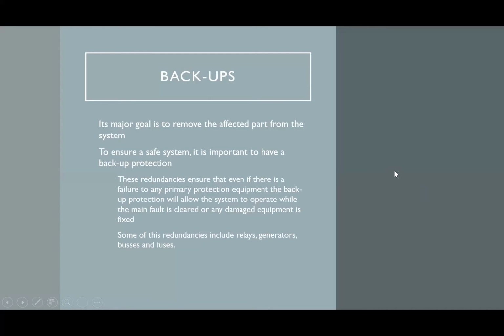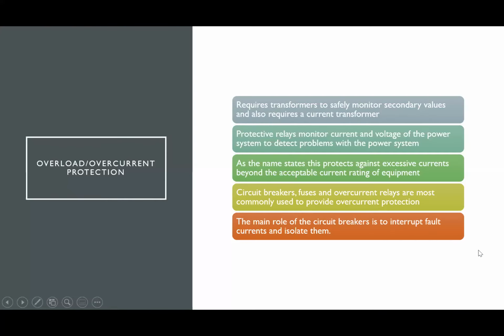And then we'll talk about backups. Its major role is to remove the affected part of the system to ensure a safe system. It is important to have backup protection. We've heard of different backups, even in our computers, the form of protection that protects our data. But it also has redundancies. These redundancies ensure that even if there is a failure in any primary protection equipment, the backup protection will allow the system to operate while the main fault is cleared or any damaged equipment is fixed. Some of these redundancies include relays, generators, buses, and fuses.